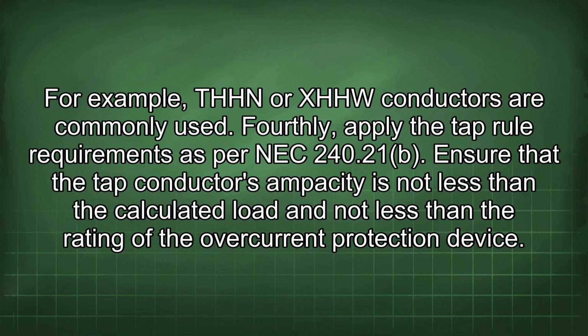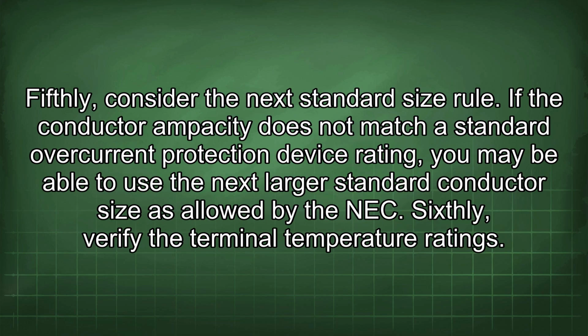Ensure that the tap conductor's ampacity is not less than the calculated load and not less than the rating of the overcurrent protection device. Fifthly, consider the next standard size rule. If the conductor ampacity does not match a standard overcurrent protection device rating, you may be able to use the next largest standard conductor size as allowed by the NEC.